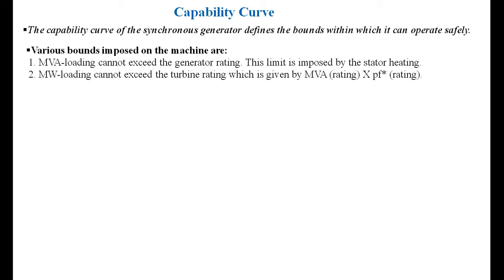The second limitation is that MW loading cannot exceed the turbine rating, which is given by the MVA rating multiplied by the power factor. That is, the megawatt output of a generator, given by MVA times power factor, should not exceed the turbine rating which is driving the generator, so that there should not be overloading. The turbine rating is given by the MVA output of the alternator multiplied by the power factor.